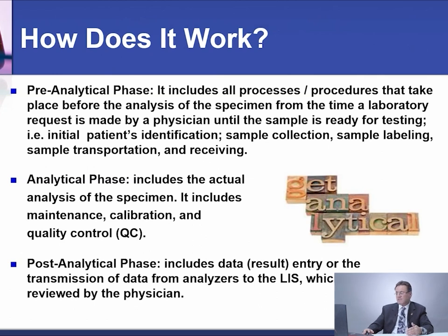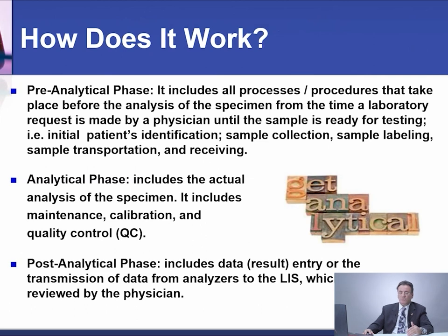The analytical phase includes the actual analysis of the specimen — it includes maintenance, calibration, and quality control. For the post-analytical phase, it includes data or result entry and the transmission of data from the analyzer to the LIS or HIS, which will be reviewed by the physician.